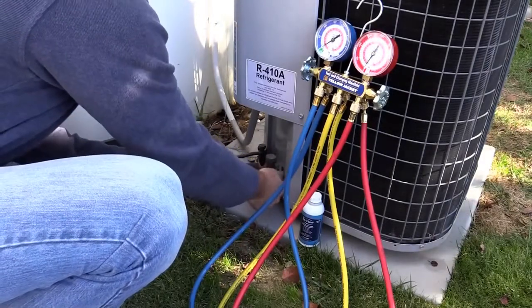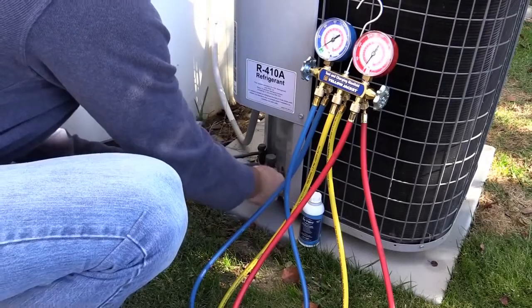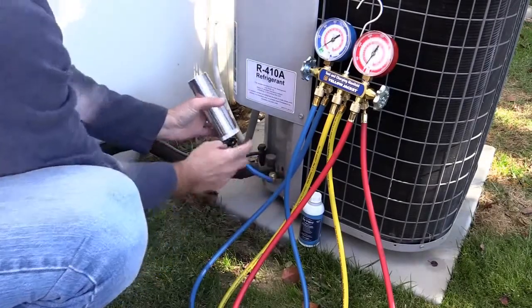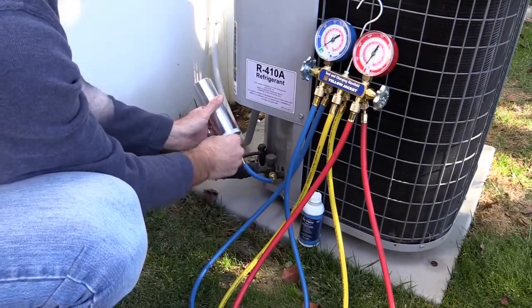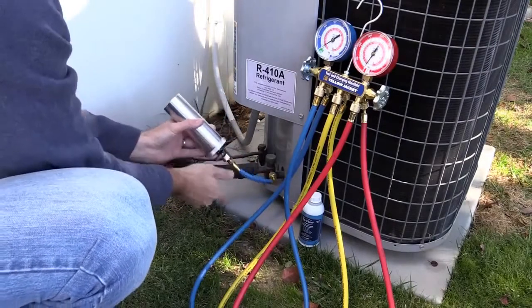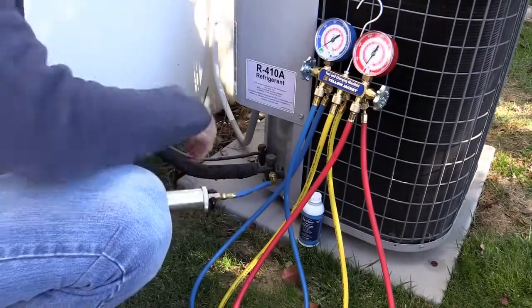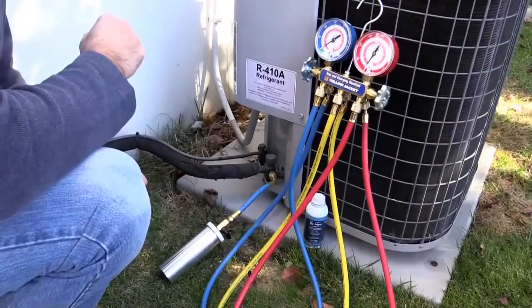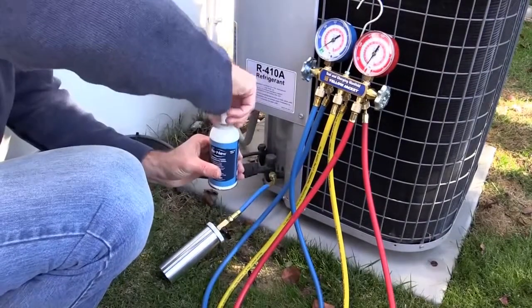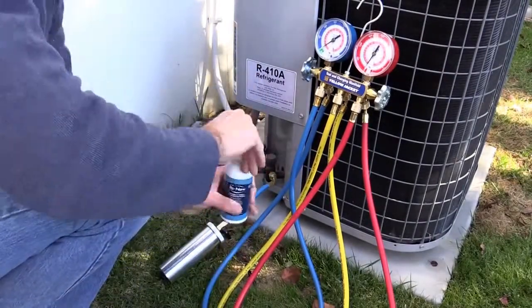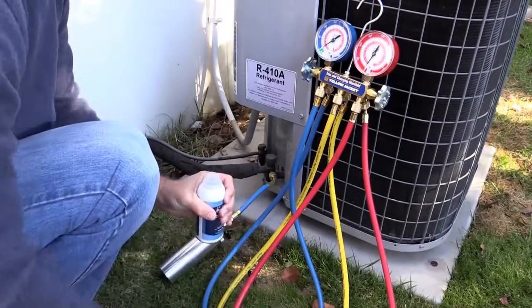Connect the 1/4 inch SAE fitting of the blue hose on the injector to the suction service port of the system. Once connected, quickly open and close the hand valve on the injector to chase the remaining air out of the hose. Open your container of new Nu-Calgon AC Renew and pour 4 fluid ounces into the open end of the injector tool.